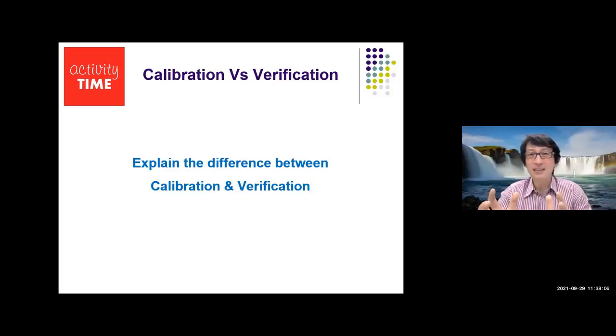When you do calibration, you need a standard. Now, what is a standard? A standard can come in many forms. It can be a standard for weight, berat. It can be a standard for length. It can be a standard for force. It can be a standard for resistance value, as in the resistor. It can be in many, many different forms, depending on what you want to calibrate. But when you do calibration, you must have a standard.